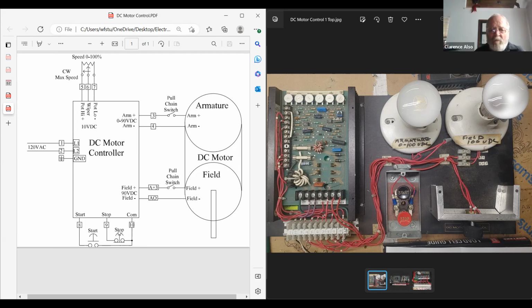So if that's normally closed, and you're not touching it, with your ohm meter leads on 9 and 10, you should see zero, right? And with your meter still hooked up that way, if I push that stop button, what are you expecting it to say? OL, okay? See the difference? Did you just prove that that stop switch worked correctly? Yeah. Okay, so that's not the problem.